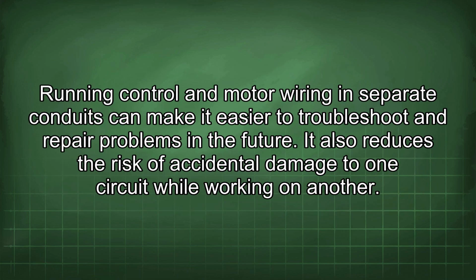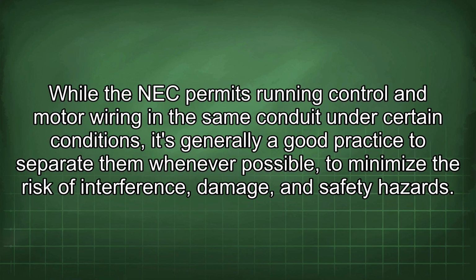Running control and motor wiring in separate conduits can make it easier to troubleshoot and repair problems in the future. It also reduces the risk of accidental damage to one circuit while working on another. While the NEC permits running control and motor wiring in the same conduit under certain conditions, it's generally a good practice to separate them whenever possible to minimize the risk of interference, damage, and safety hazards.